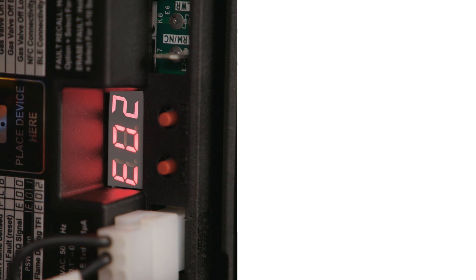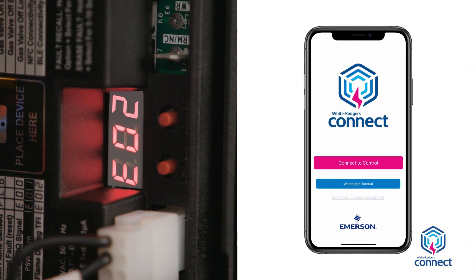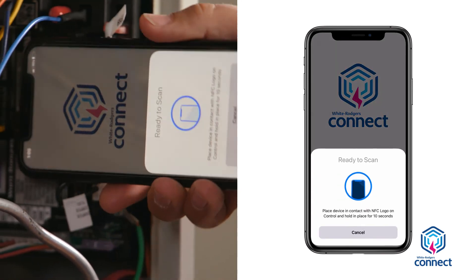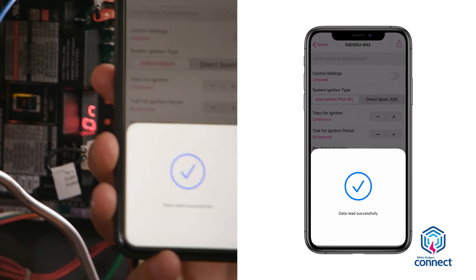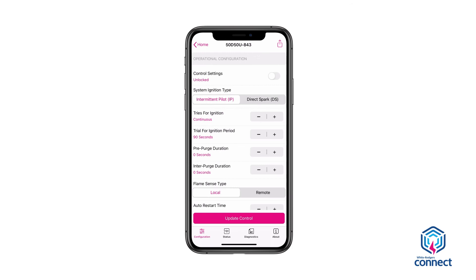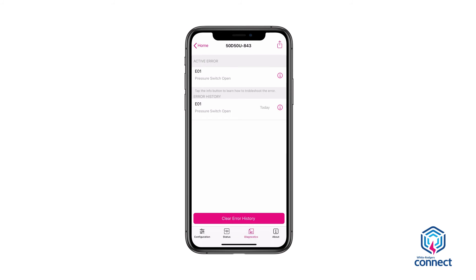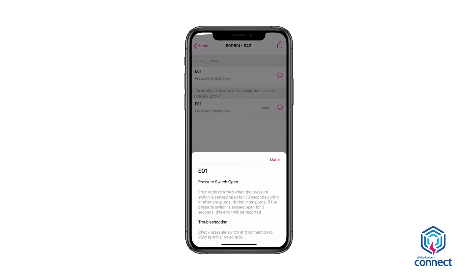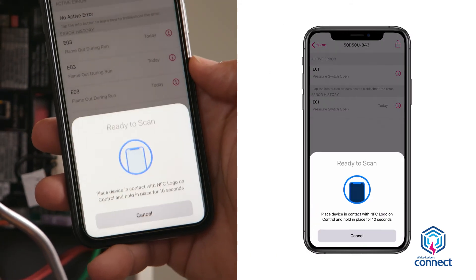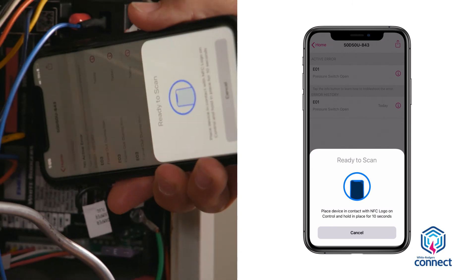Fault code errors can be recalled through the White-Rodgers Connect mobile app. Open the app and select the Connect to Control button. Place the mobile device near the NFC logo on the module and wait until a checkmark appears showing the connection was successful. The app will then display the module's settings configuration page. To see any errors, select the Diagnostics tab. Errors will be listed with the most current at the top. For detailed information and troubleshooting tips, select the eye icon by the fault. To clear errors in the app, tap the Clear Error History button, place the device in contact with the NFC logo on the module, and wait for the checkmark to appear.